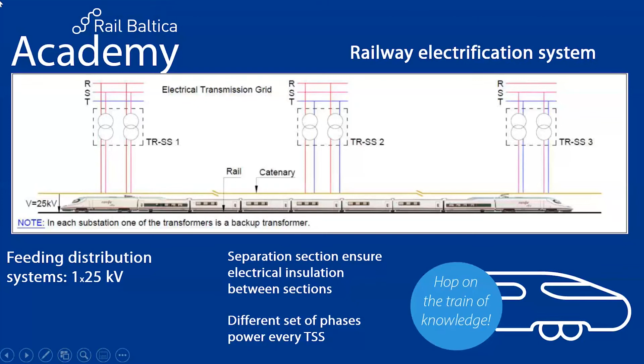Railway electrification needs only 2 phases, because we power the trains between the catenary and the rails, while the electrical transmission grid uses 3 phases. We can have connection problems, so we have to connect only 2 phases. For this reason we have to alternate the phase, not using the same phase in different substations - this is a request from the grid that we'll detail further. So you can see how it's organized for this 1x25 solution.